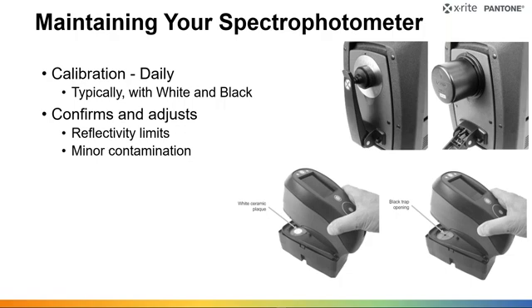And it also adjusts, right? There may be some minor contamination. A lamp, as it ages, emits light slightly differently, and so it's adjusting for those things. That's what your daily calibration is. Some instruments don't require it daily. Some instruments, you might be doing it every 4 hours, right? A lot of it depends on the device and the use case. But that calibration is making sure, yep, it's still measuring in that same range of reflectivity correctly.